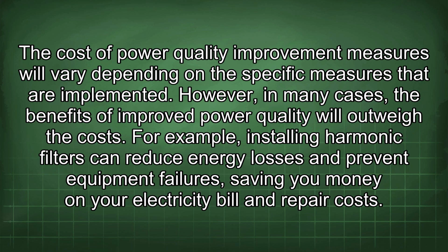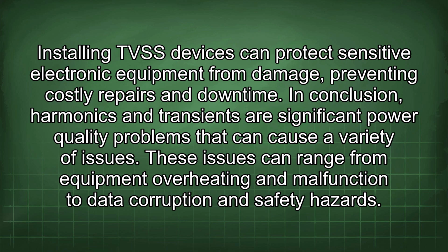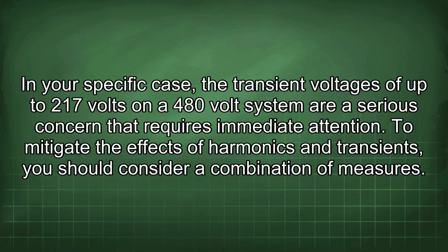For example, installing harmonic filters can reduce energy losses and prevent equipment failures, saving you money on your electricity bill and repair costs. Installing TVSS devices can protect sensitive electronic equipment from damage, preventing costly repairs and downtime. In conclusion, harmonics and transients are significant power quality problems that can cause a variety of issues. These issues can range from equipment overheating and malfunction to data corruption and safety hazards. In your specific case, the transient voltages of up to 217 volts on a 480 volt system are a serious concern that requires immediate attention.